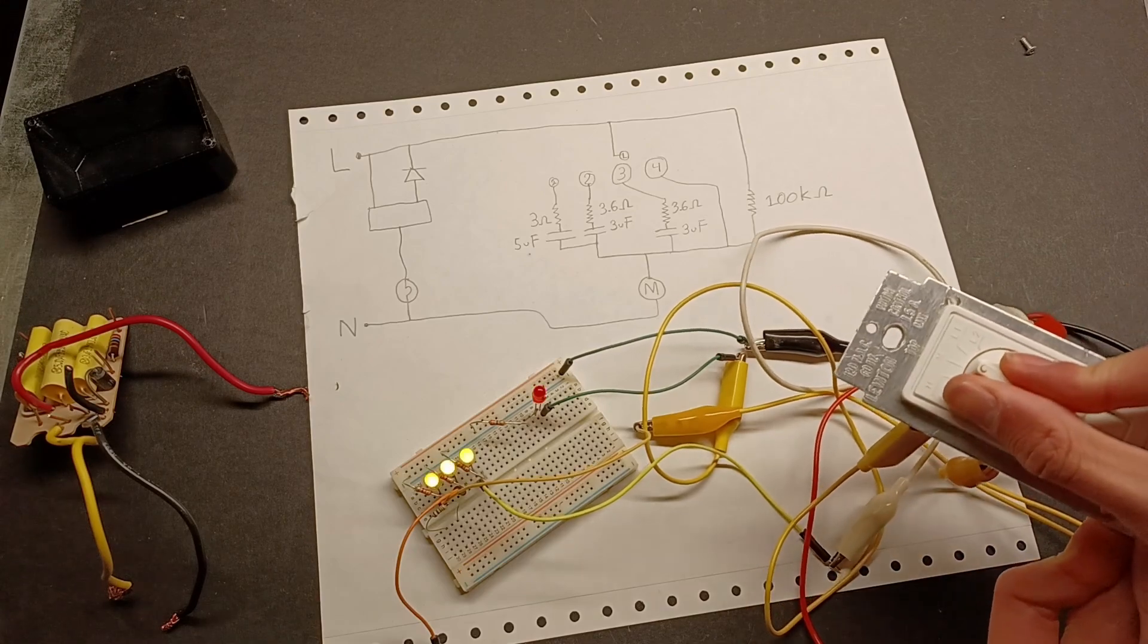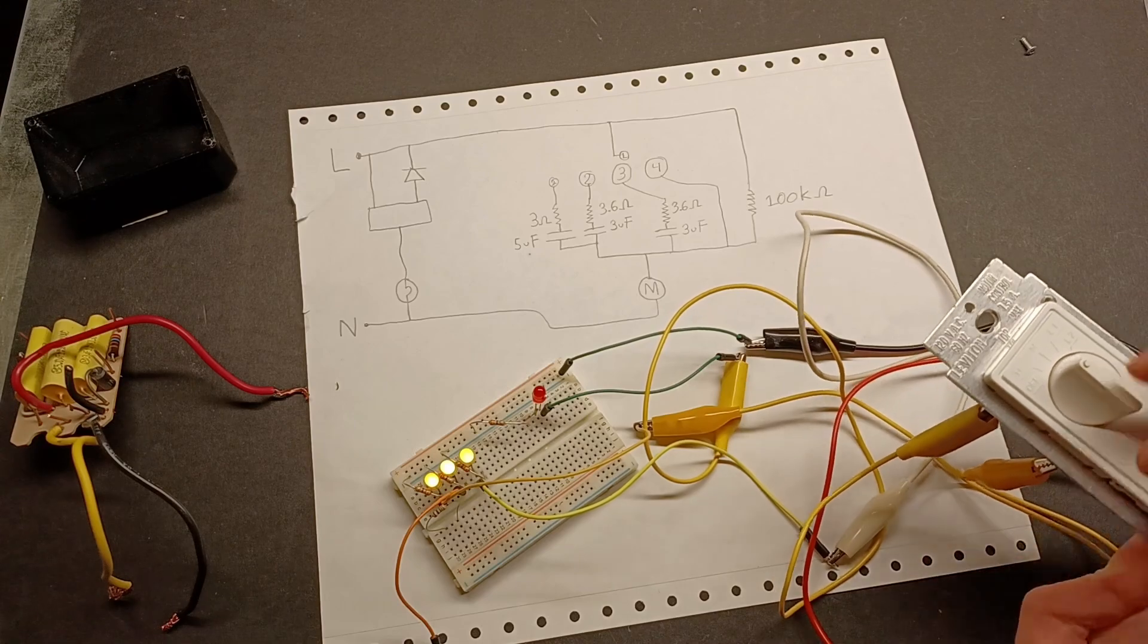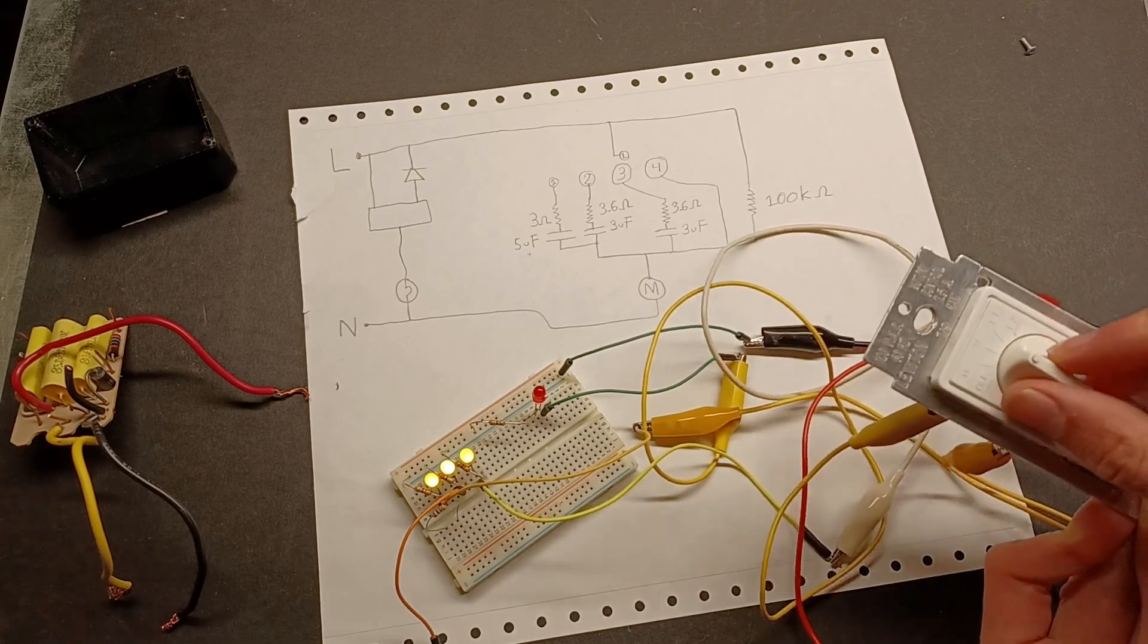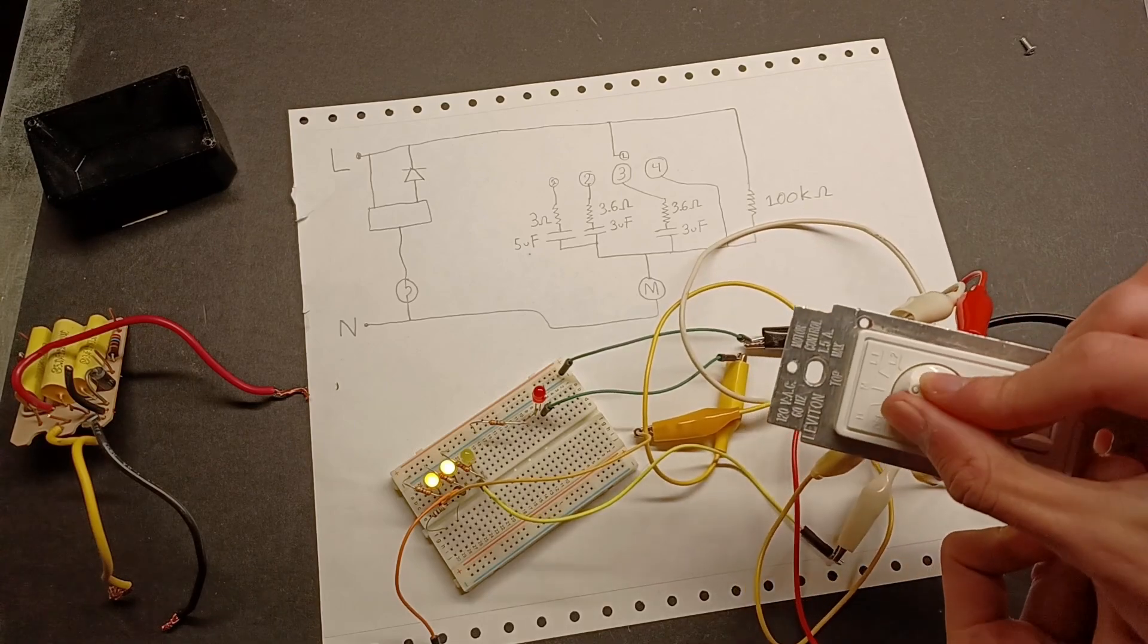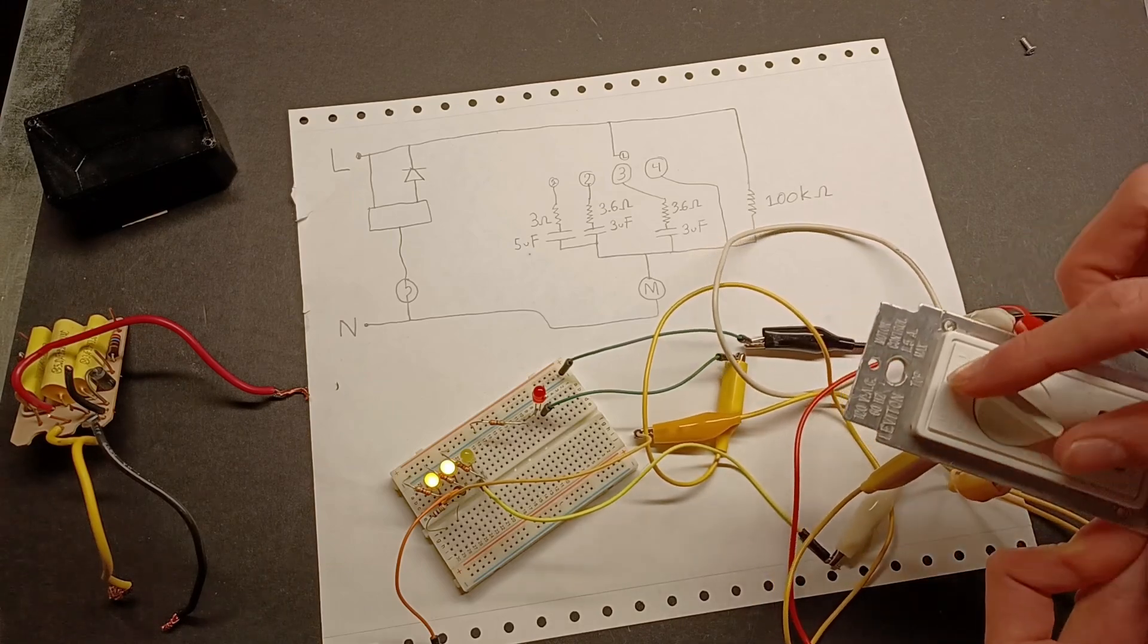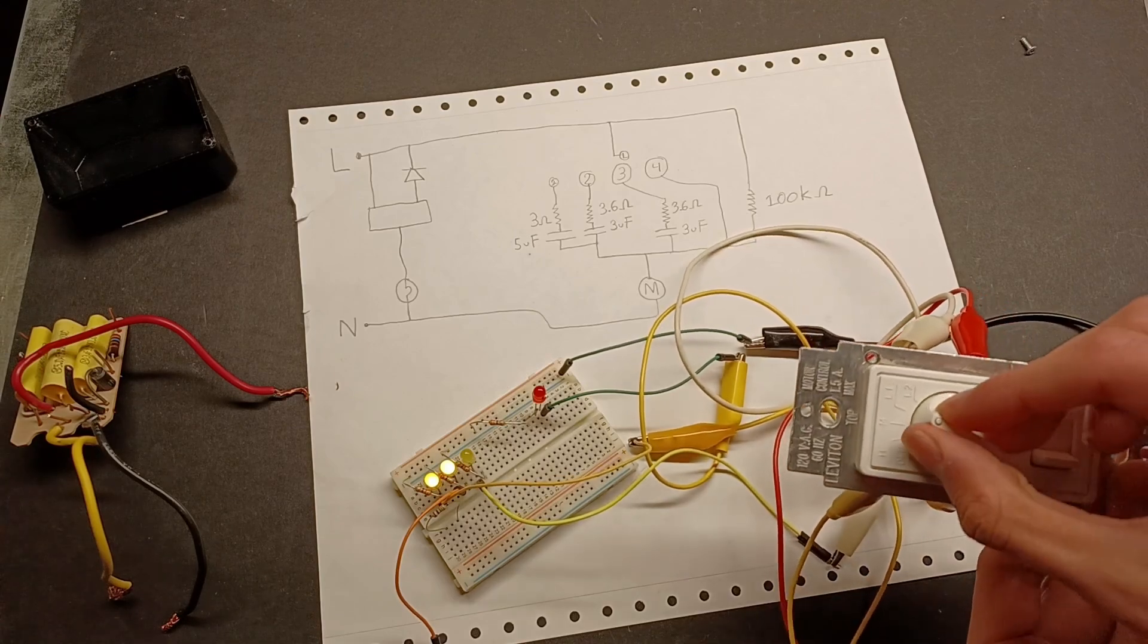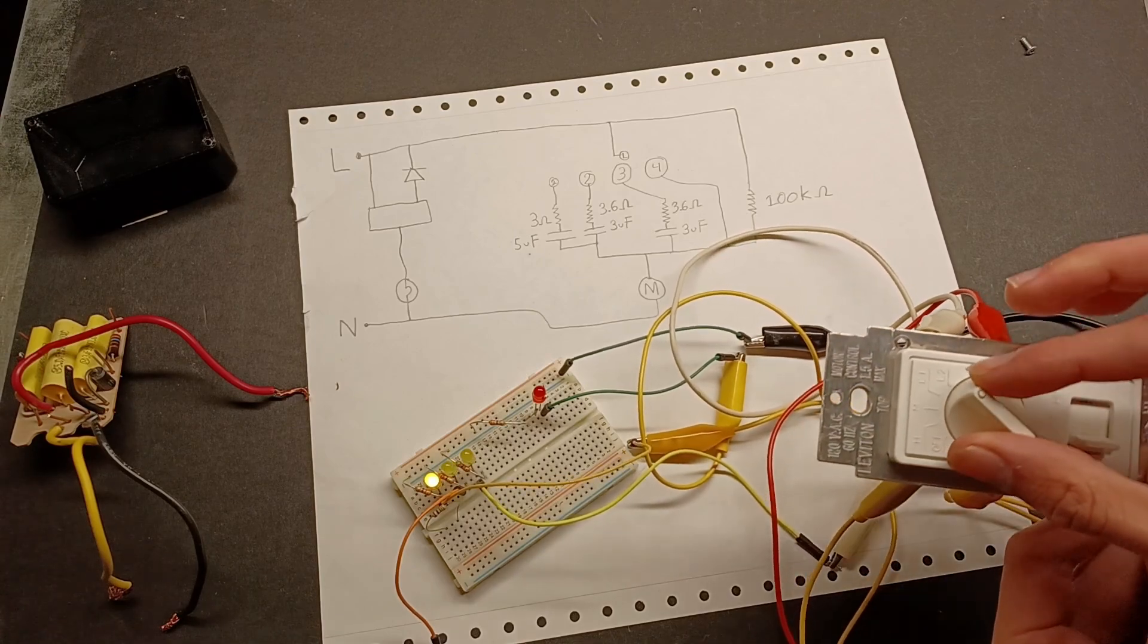If I turn the switch to medium, terminals 1, 2, and 3 all get powered. Turn it to low setting 1. Only terminals 1 and 2 get powered. If I turn it to low setting, only terminal 1 gets power.